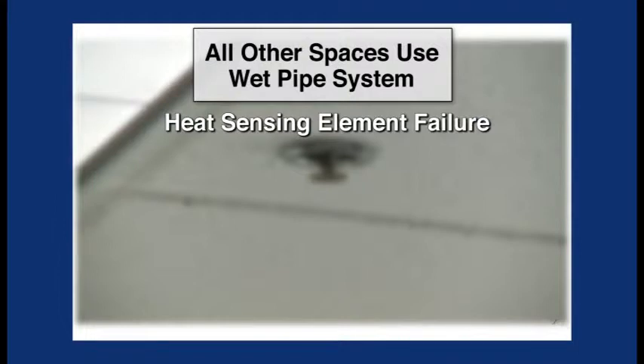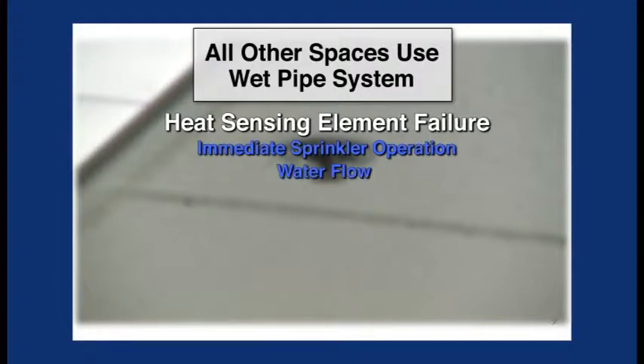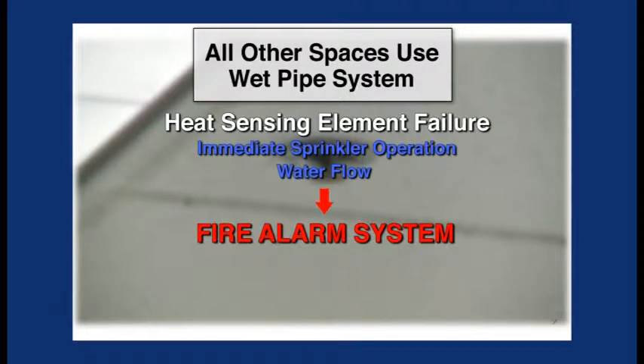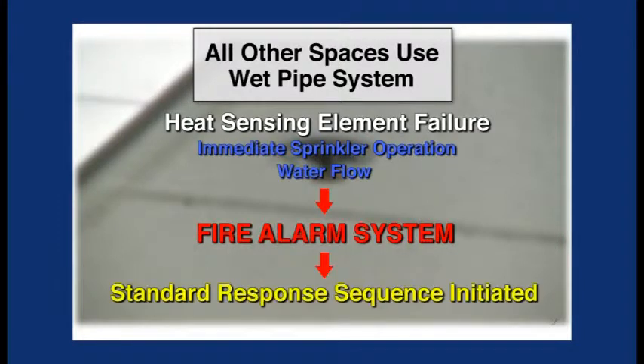Failure of the heat sensing element at any sprinkler head in these areas will result in immediate sprinkler operation in the affected area. Water flow within an individual zone will initiate a fire alarm via the fire detection and alarm system. If the tamper switch at any system component is activated, or if the low water pressure switch is activated, this signal will cause a trouble condition on the fire alarm control panel, and its identification will be annunciated. The alarm sequence will be activated.